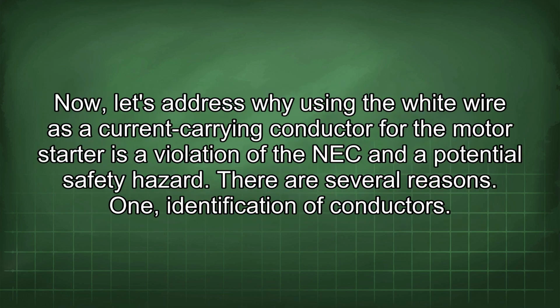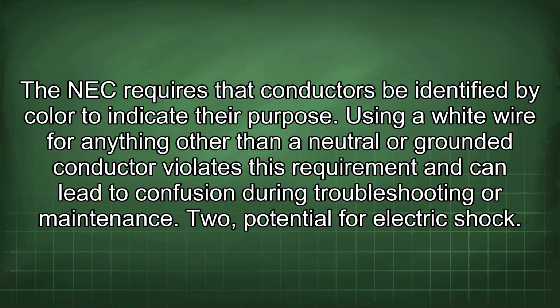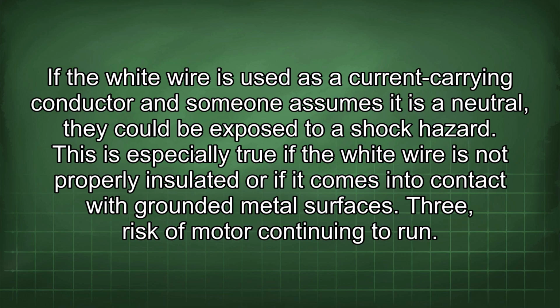Now, let's address why using the white wire as a current-carrying conductor for the motor starter is a violation of the NEC and a potential safety hazard. There are several reasons. 1. Identification of conductors. The NEC requires that conductors be identified by color to indicate their purpose. Using a white wire for anything other than a neutral or grounded conductor violates this requirement and can lead to confusion during troubleshooting or maintenance. 2. Potential for electric shock. If the white wire is used as a current-carrying conductor and someone assumes it is a neutral, they could be exposed to a shock hazard.